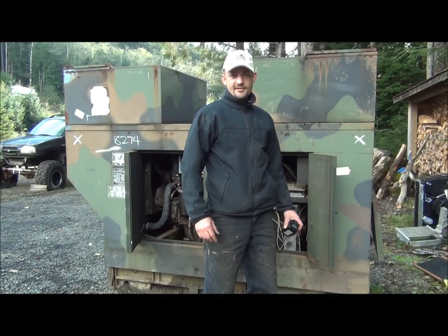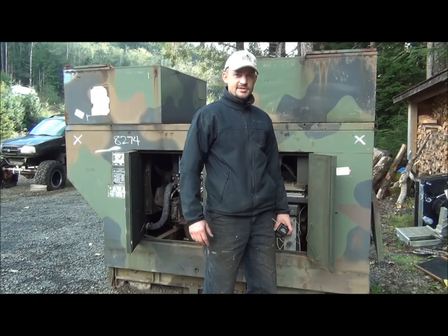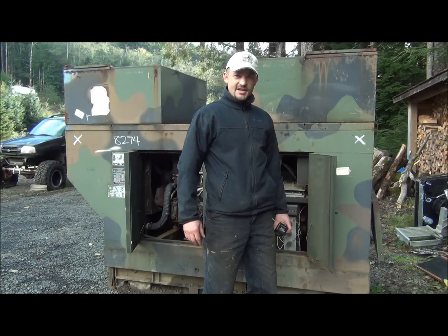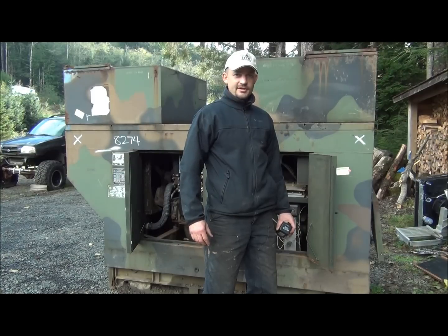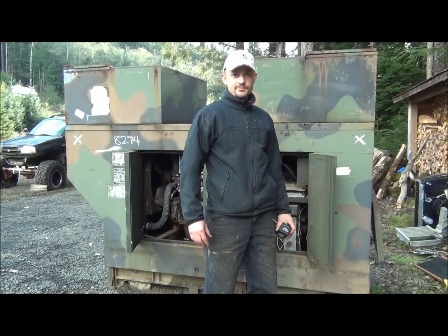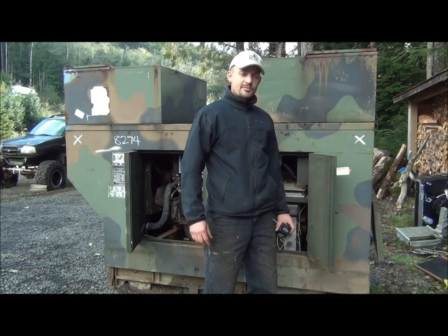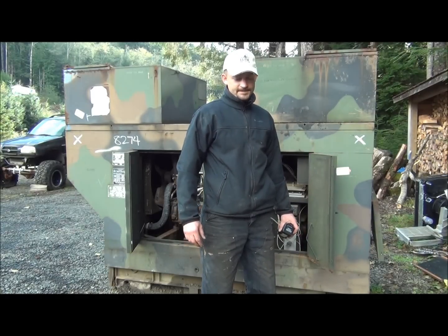So now that we have that adjusted properly, I set the generator for 60 hertz and started it several times, and I didn't have a single overvoltage trip. So that was definitely the problem. Running the generator at such a high RPM was causing the overvoltage trip on the startup. So now that we're running it at the proper RPM, we don't have that problem anymore.